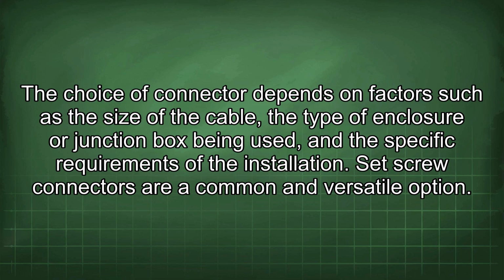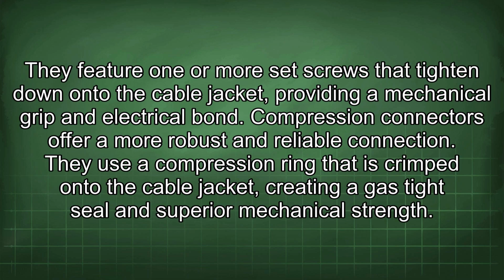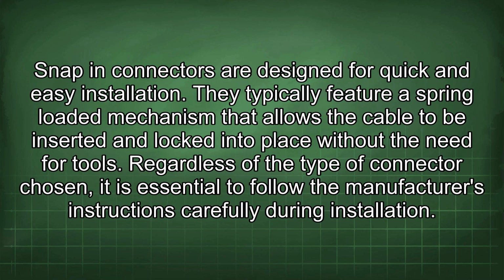Set screw connectors are a common and versatile option. They feature one or more set screws that tighten down onto the cable jacket, providing a mechanical grip and electrical bond. Compression connectors offer a more robust and reliable connection. They use a compression ring that is crimped onto the cable jacket, creating a gas-tight seal and superior mechanical strength. Snap-in connectors are designed for quick and easy installation. They typically feature a spring-loaded mechanism that allows the cable to be inserted and locked into place without the need for tools.